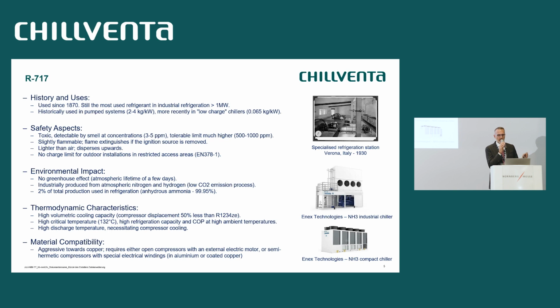In terms of other characteristics, I will not go through this list, but what is important to highlight is that, yes, ammonia is toxic, but it's detectable at a very small amount. Just 3 to 5 ppm, you can detect a pungent smell. On the other hand, the tolerability limit, when it poses a risk for health, is much higher, about 500 or 1,000 ppm. So there is a big gap, and that's why ammonia has been safely used for decades, mainly in industrial refrigeration.